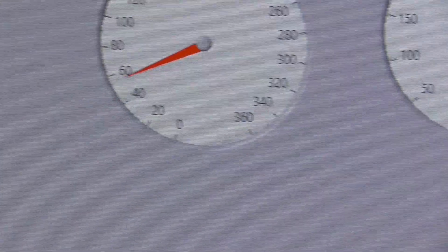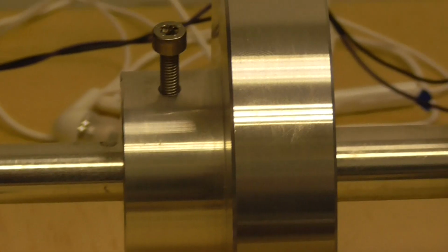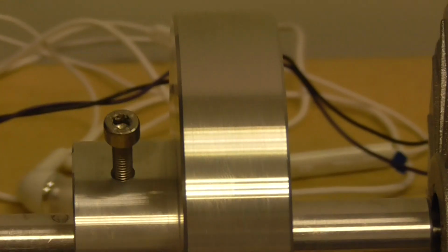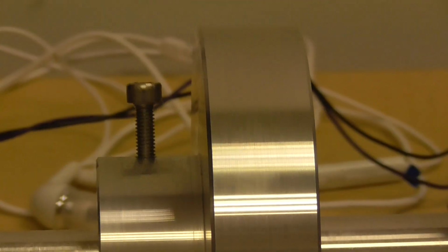Oops, there she goes. Notice the current here has shot up to 3.7 amps. I don't want to keep it like that for very long. Over here you see the dial's going mad. Normally there are no oscillations. That's when there's a little bit of a squeaky noise, and that's when the gain is a bit on the high side. I can keep turning it up. You can hear that. This is due to structural resonance in the windings of the motor. Not very nice. I don't want to keep the gain that high either.